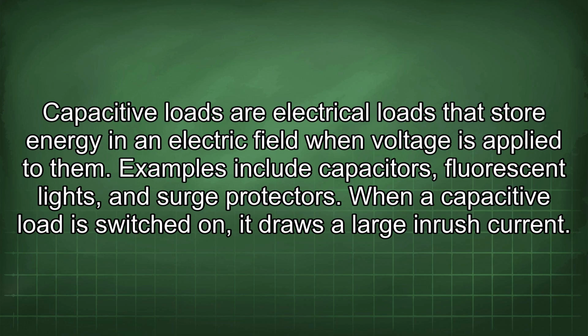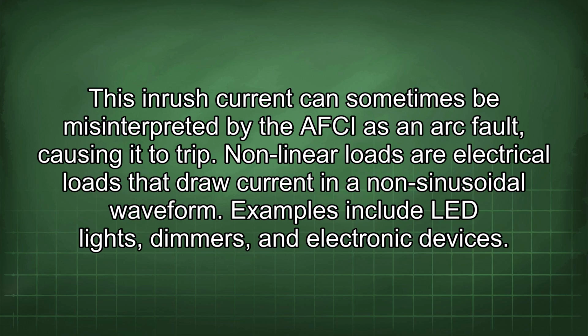Capacitive loads are electrical loads that store energy in an electric field when voltage is applied to them. Examples include capacitors, fluorescent lights, and surge protectors. When a capacitive load is switched on, it draws a large inrush current. This inrush current can sometimes be misinterpreted by the AFCI as an arc fault, causing it to trip.